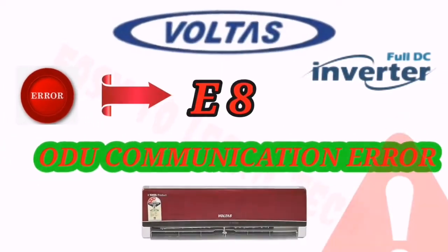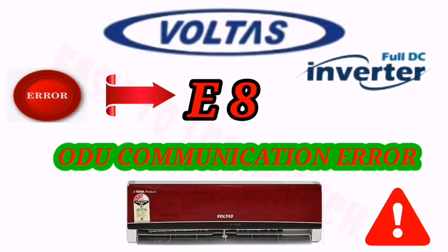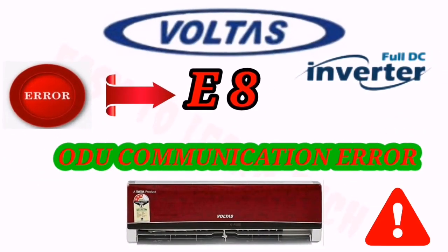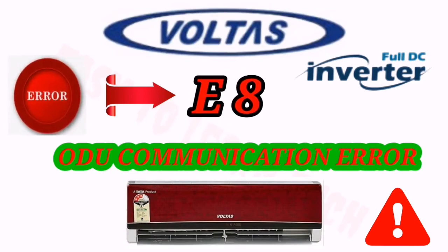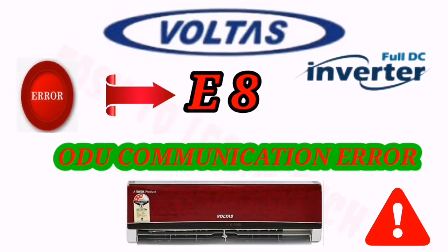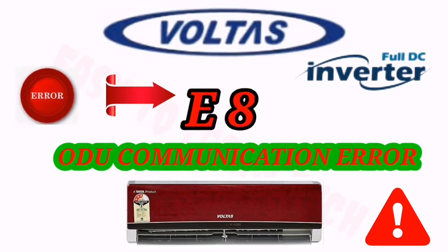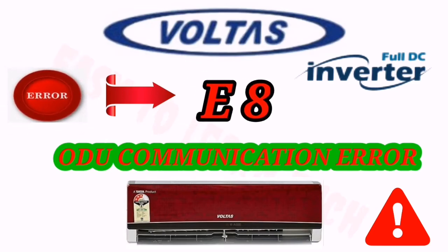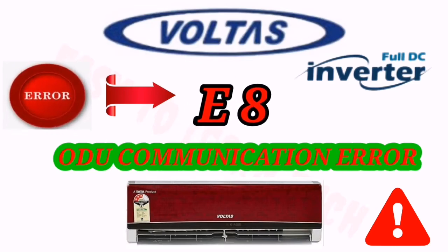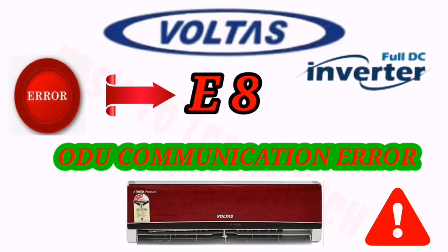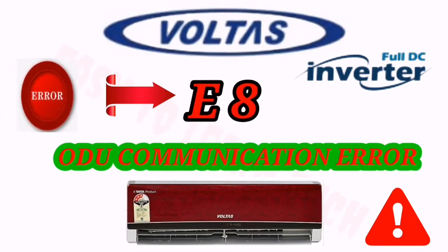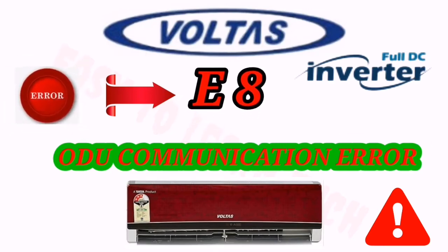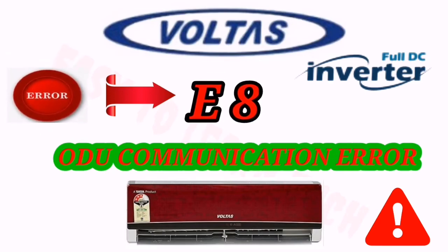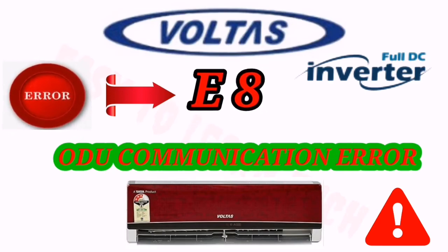Let's see the next error code. When you see E8 in your display, it means outdoor communication problem. This is mainly only for the outdoor. First of all, you have to check the indoor and outdoor model names. If they do not match, you have to change the wrong unit. If your model number for the indoor is different from the outdoor, then you have to change the indoor or outdoor so that both units are of one model.